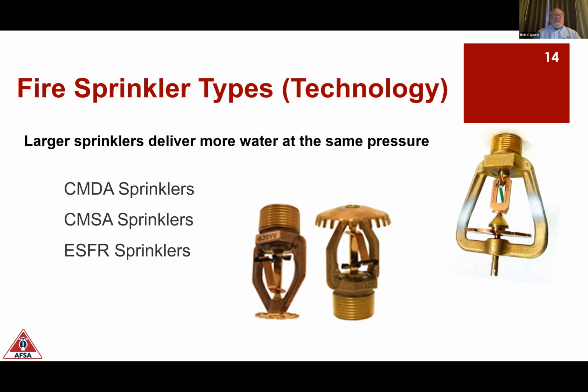The next is called the CMSA, which is an acronym for Control Mode Specific Application Sprinkler. It is a sprinkler specifically designed for storage applications. And lastly, we have the ESFR, which is called an Early Suppression Fast Response Sprinkler. Larger sprinklers deliver more water at the same pressure.